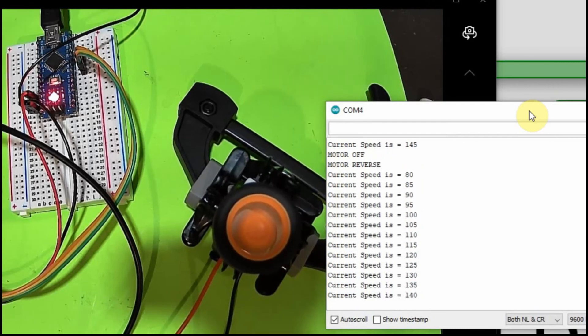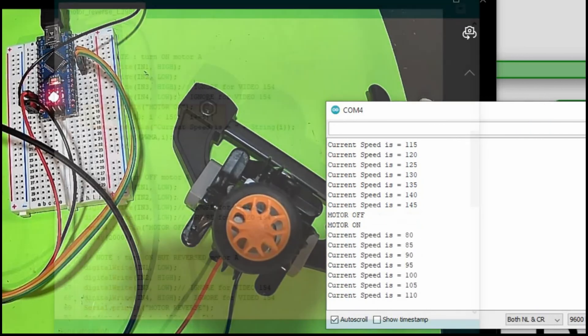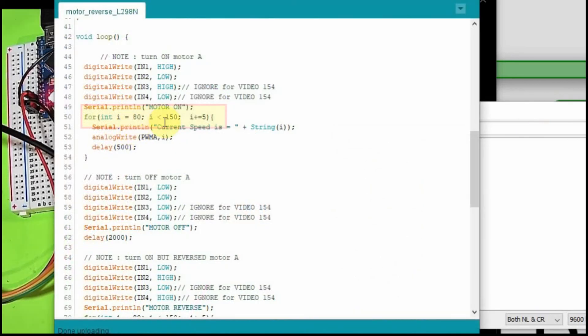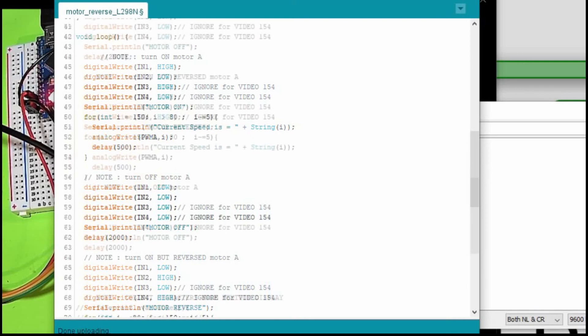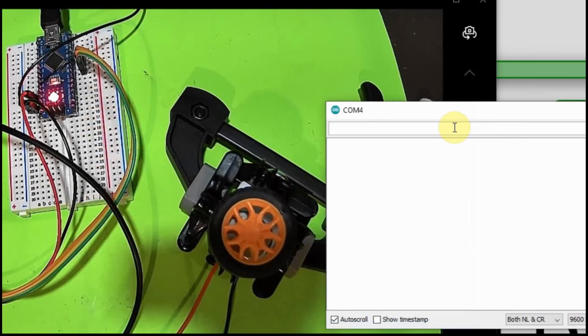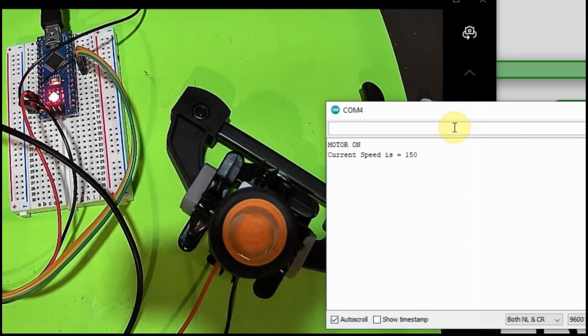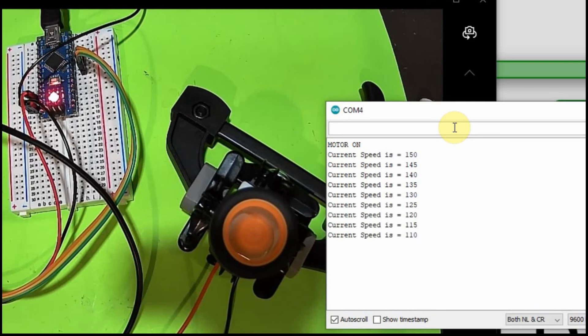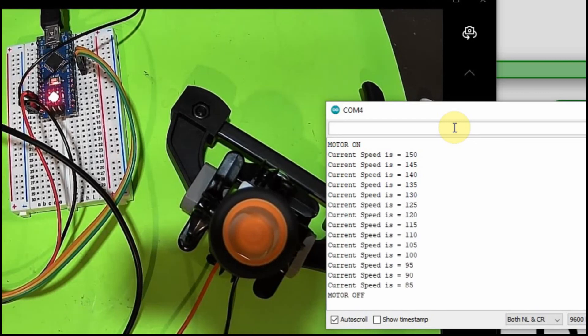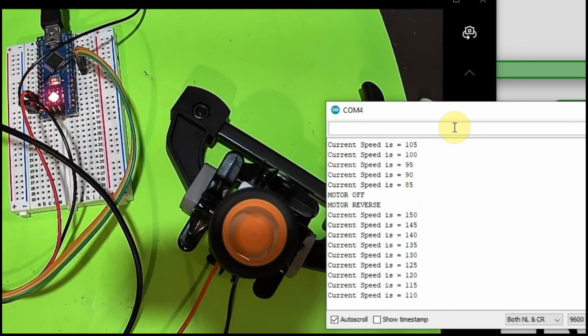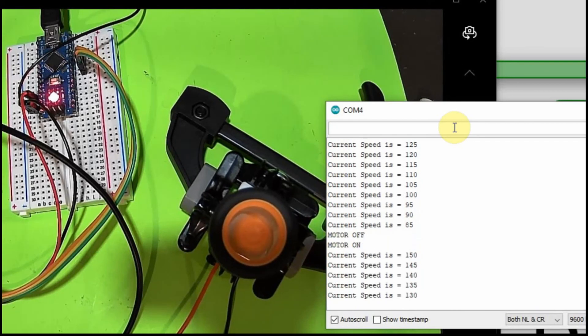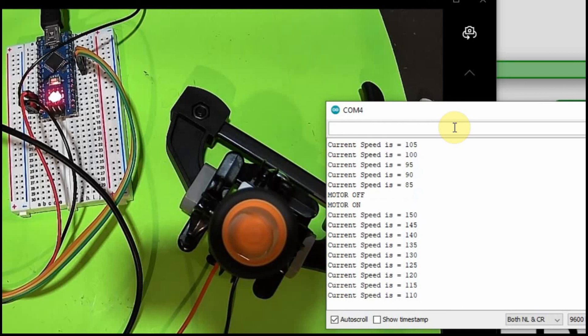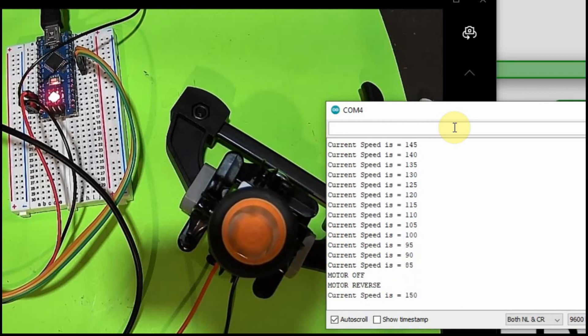But now I want to show you what happens when you do it in reverse. So instead of going from 80 to 150, we're going to go from 150 down to 80. So now based upon that, you would expect it to start fast and then about 100 drop out. So it's starting just like we thought, but then you'll notice it just keeps going. And that's because once the motor has started, it's easier to keep it running than it is to get it started.